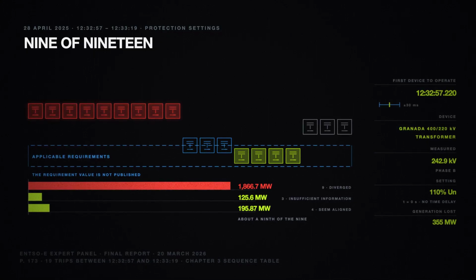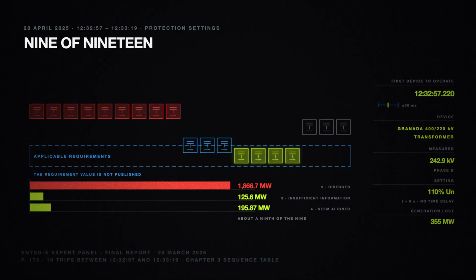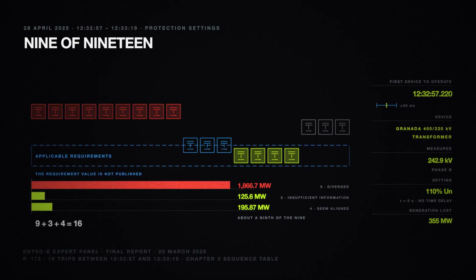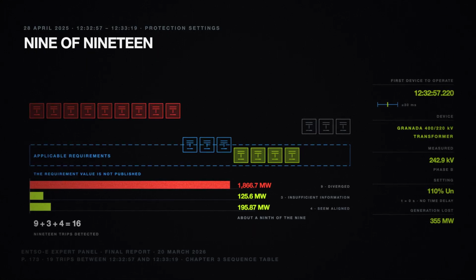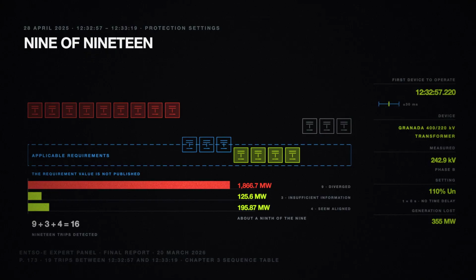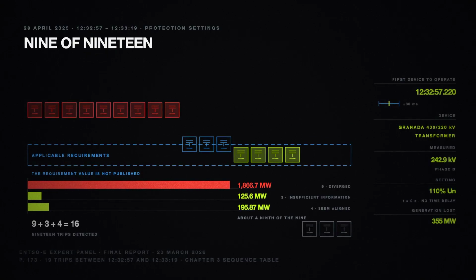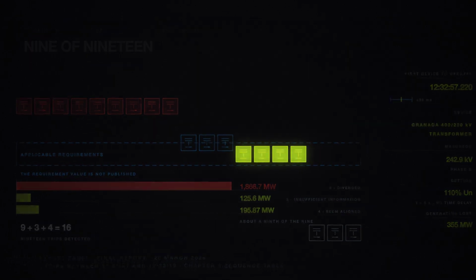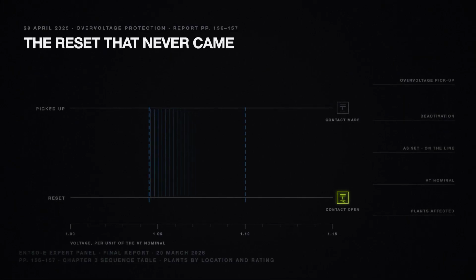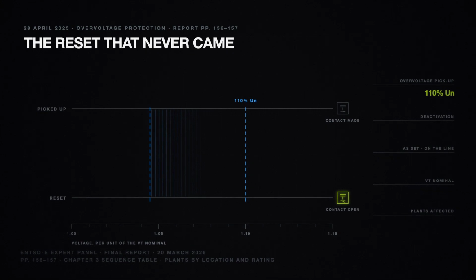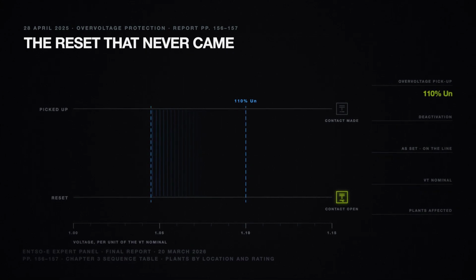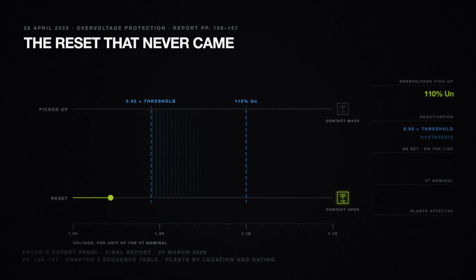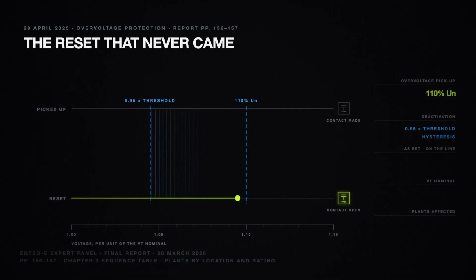Now count the groups, 9 and 3 and 4. That is 16. There were 19 trips. The report's own arithmetic reaches 16 of them and stops. 3 of the 19 belong to no group at all. A relay picks up 1/10 above nominal, and it does not let go until the voltage has fallen 5% below the level that picked it up. That gap is hysteresis, and it is the reason setting a relay higher does not fix this.